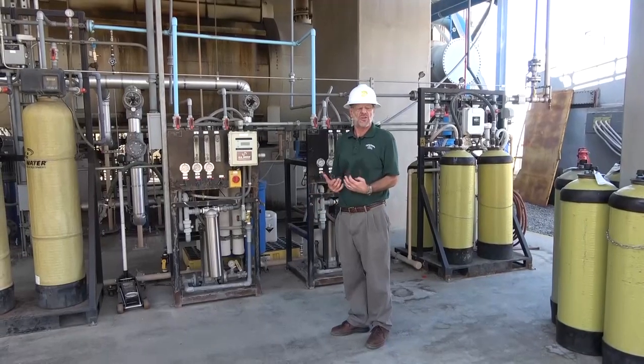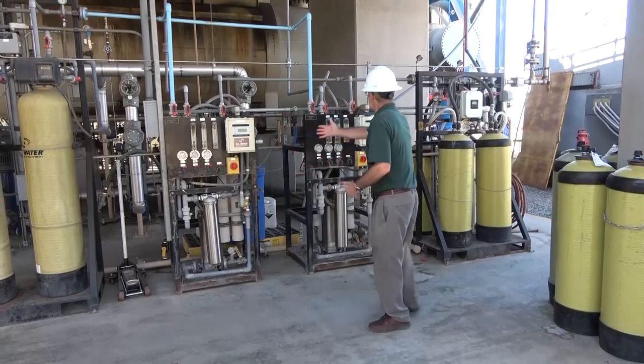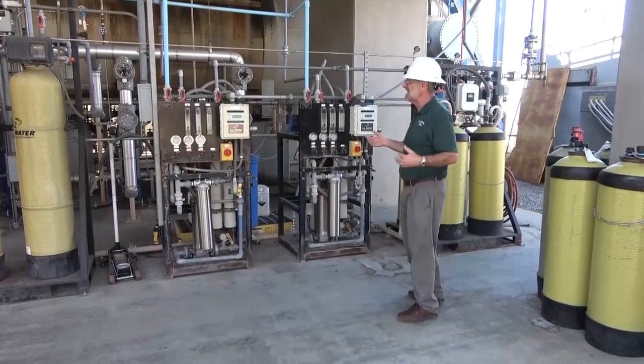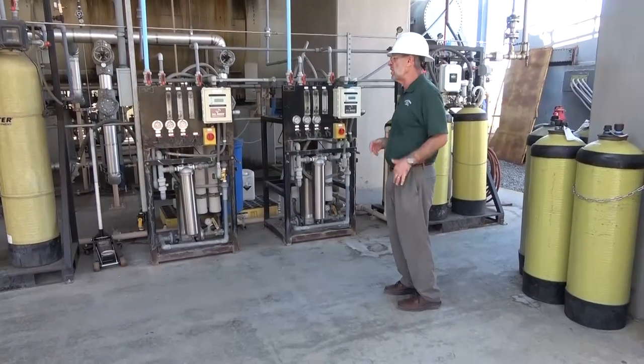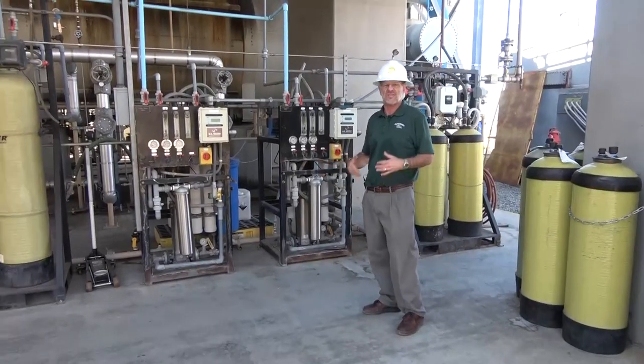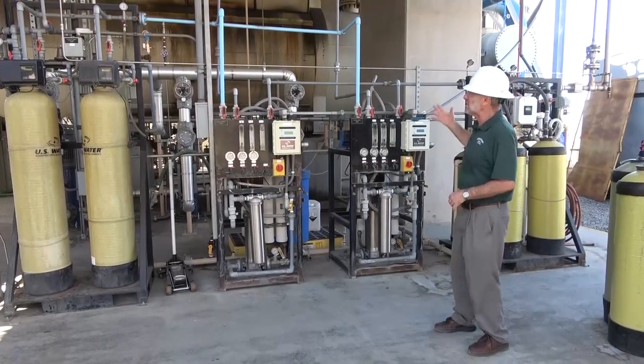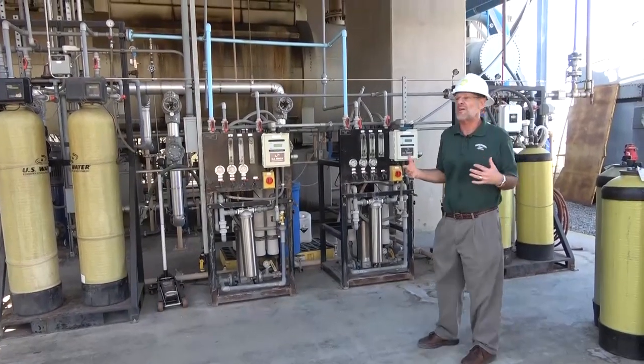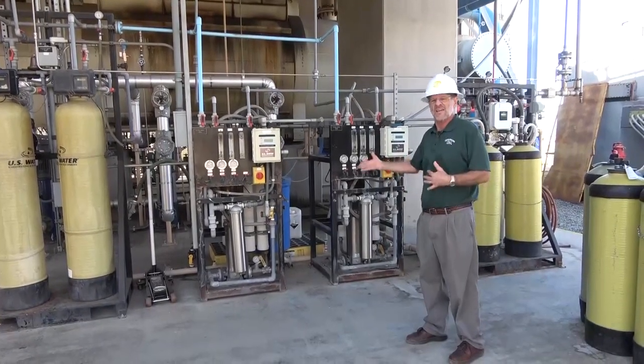Like all steam power plants, water must be very pure. This modern purification system includes two reverse osmosis systems and two demineralizer beds — one likely a cation bed, the other an anion bed — which absorb remaining charged particles from the water. After going through RO and the demineralizers, the very well purified water is stored in a purified water tank elsewhere on site.